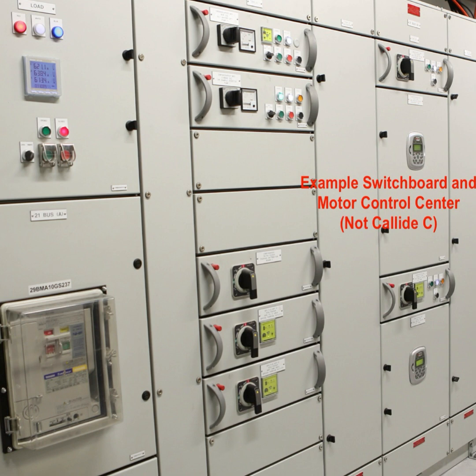Better to have a controlled release of pressure than the pressure have nowhere to go and you get an uncontrolled rupture in an unknown weak point in the chassis. As an additional protection measure, regularly attached to these arc flaps is a limit switch that triggers when the flap opens, and the limit switch, which is normally closed, goes open circuit when the flap opens. This circuit then feeds into an arc flap protection relay from the circuit breaker's battery-backed-up DC source, which, in this case, was the same 220-volt DC source from Unit C4's DC main bus.